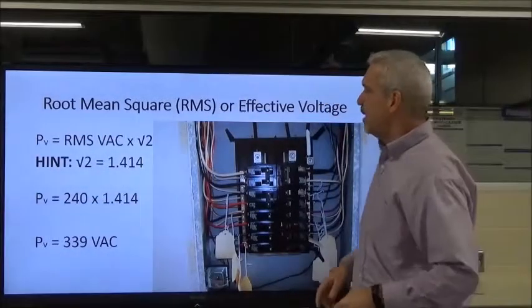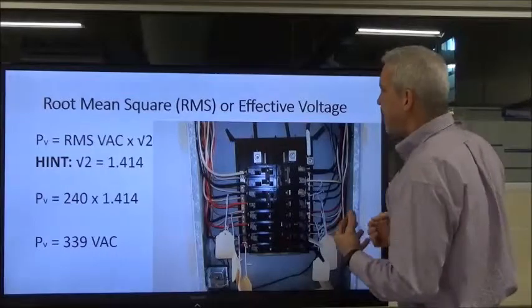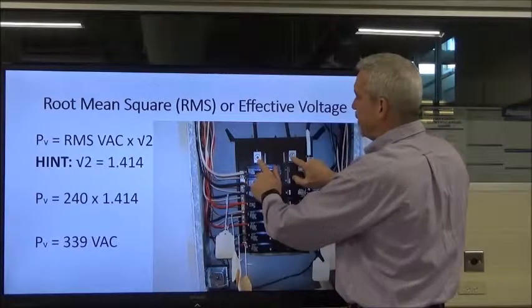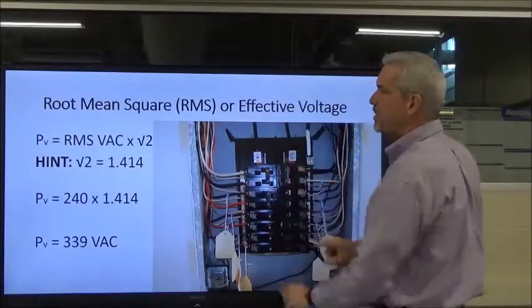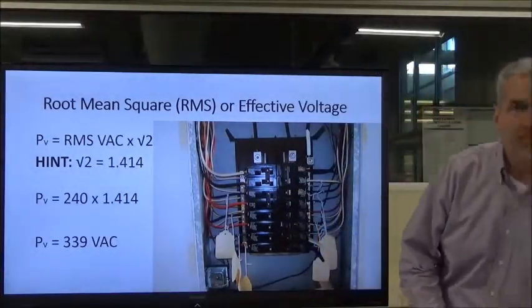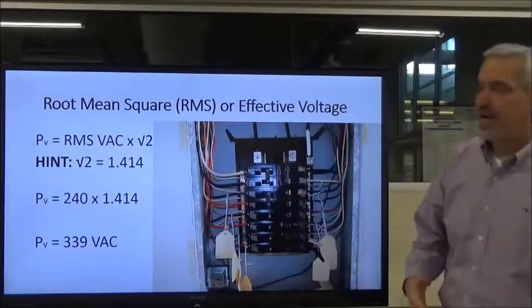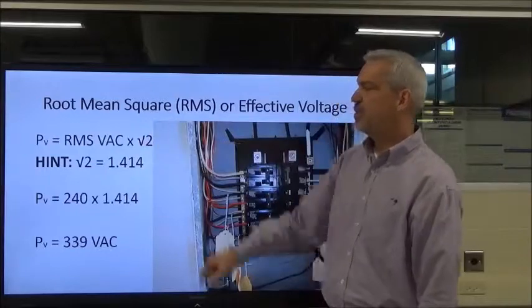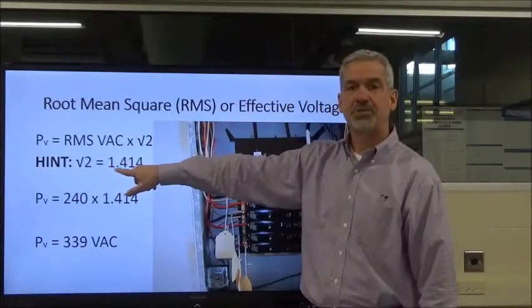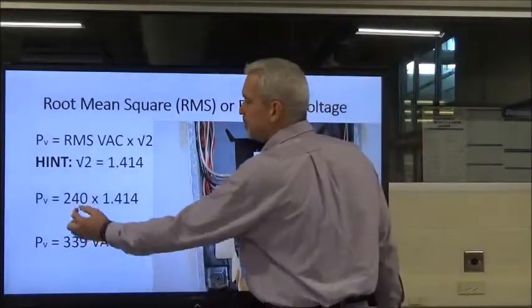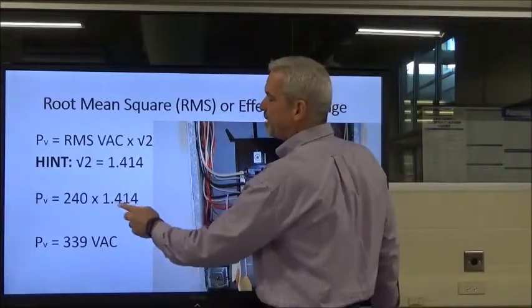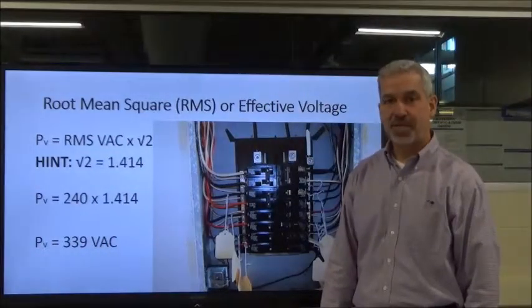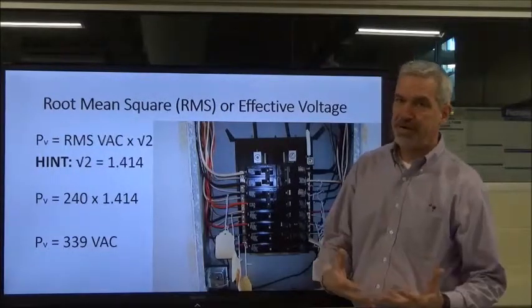Now let's put this in a practical application. We've got power coming from the power company — they feed us two legs of 120 volts, and we put our meter across here and measure 240 volts. Remember, our meter is root mean square. So we take that RMS value of 240 volts AC and multiply by the square root of two, which is 1.414. That gives us a peak value of 339 volts AC — that's really what's coming into the house. What we're measuring with our meter, though, is root mean square.